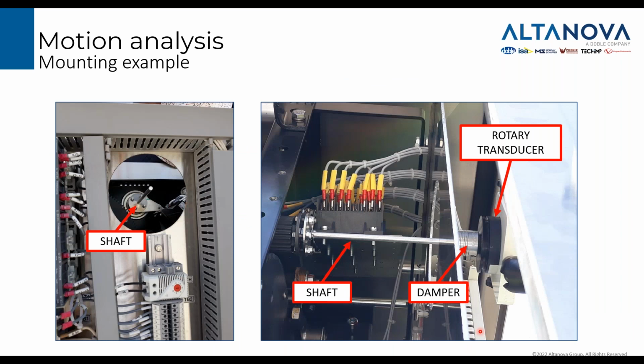There are some mounting examples. So this is one possible situation you can find, but of course in the field there are so many different circuit breakers that I'm sure that if you check your circuit breaker, the situation will be much different from the one in this example. So this is a shaft that is touching this moving part, and then we need to introduce a damper between the rotary transducer and this shaft. This guarantees the best accuracy of the measurement, but at the same time it saves the transducer itself, because the damper is also absorbing some shocks.